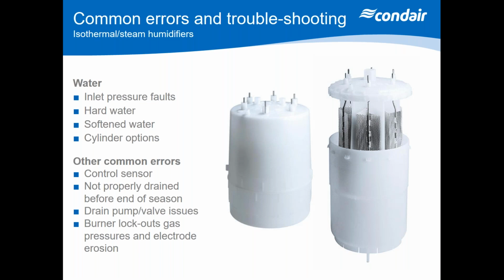The one that I see commonly all the time is people trying to exchange the raw mains water for softened water. Now, softened water, basic exchange softened water is you taking all your calcium out through a resin filter in your softener and exchanging that with sodium. And as I said earlier on, when you put your sodium into a saucepan at home, it boils very, very quickly, and you're going to find that it'll foam. And what you'll see then is foaming action and a damage in the electrodes. So softened water is, I would say, a no-no, obviously, for using with electrode boilers. You're better off sticking with raw mains water.